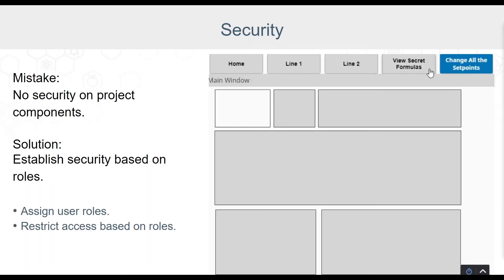Once a user is logged into a project, they have access to all windows, page views, and button clicks by default. It's very likely that you don't want everyone changing set points, and some information may be management only. It's best practice to define roles and restrict access to buttons or other components such as set point entries based on that role. It's common to assign roles by function — such as operator, supervisor, or team lead — or by lines or departments. A component can be visible but disabled, or completely hidden if the logged-in user is not a member of the required role.